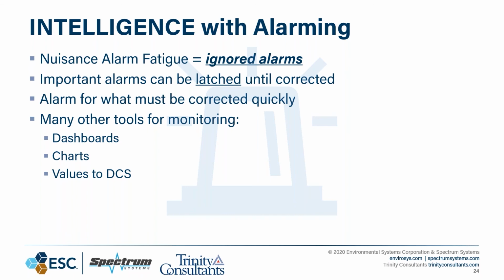Important alarms can and should be latched, meaning that the alarm message stays up there until the condition is corrected, until that fault is taken care of and the alarm goes away. An intelligent alarm is for what must be corrected quickly. And you still have other tools available to you for monitoring that. You have the dashboards, the charts, the values to your DCS and PI system, whatever you use at your facility. You should always use intelligence when you're asking to have these alarms configured on your system. And you should be studying them periodically to determine if they're truly important or if they're simply informational and can be safely ignored.